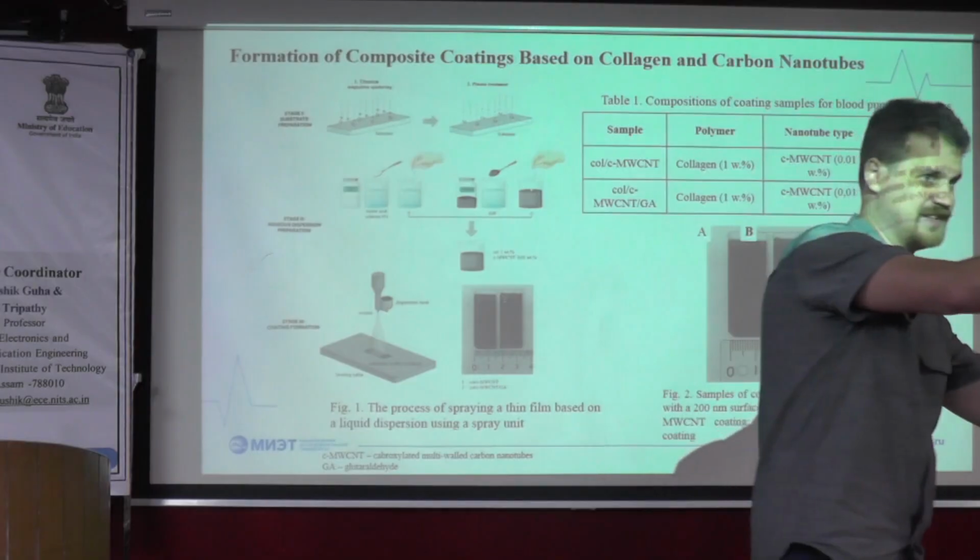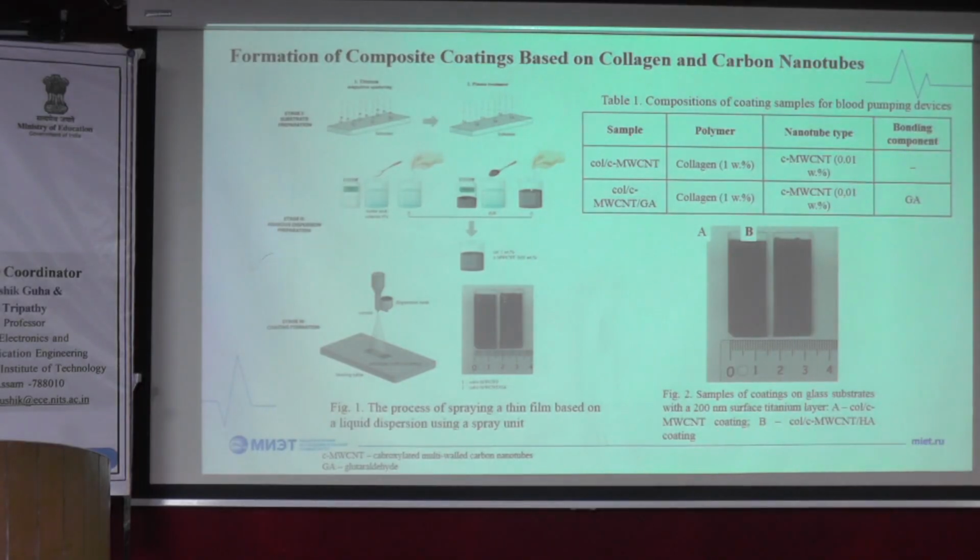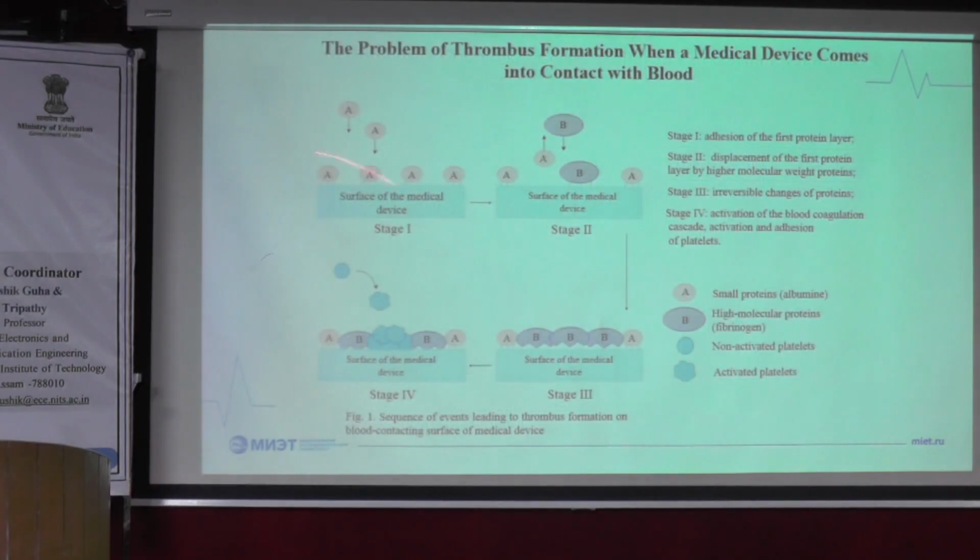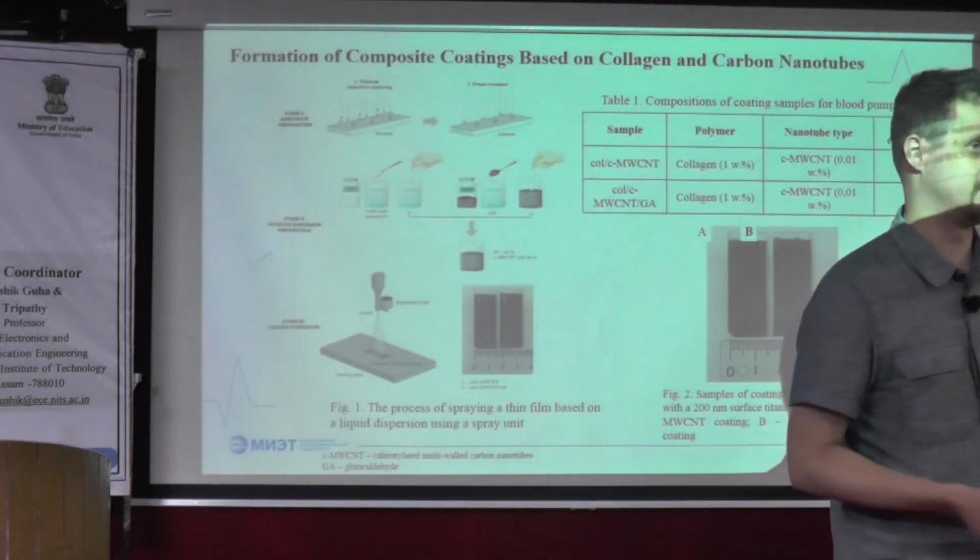This particular surface should not degrade, because the more it degrades, the bigger the chance that at some point we'll initiate the first stage of blood clotting. And if there is no surface that prevents that, then this surface can be gone, because the exploitation time is so long that blood just erases this surface. We need to take into consideration the mechanical properties of that surface.